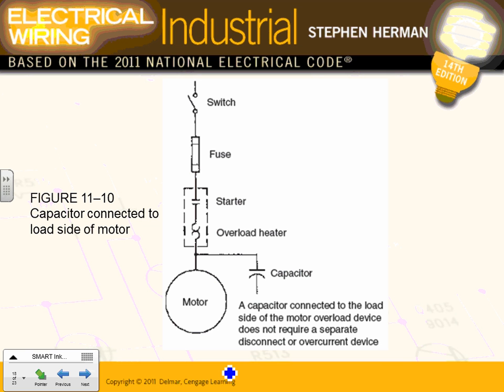When you have a capacitor, you can connect your capacitor right in here. If you connect it this way, guys, the only thing you have to pay attention to is sizing this conductor, which is 1.35 times the full load current. That's how you size the conductor for a capacitor. You take the full load current of the capacitor and multiply it by 1.35 from Article 460. Article 460 will tell you that when you size a conductor for a capacitor, you have to multiply it by 1.35. Any comments, guys? Any questions about that? And the second way of connecting them: you can connect them on the load side with the motor, right here. Then you have to adjust your overload.